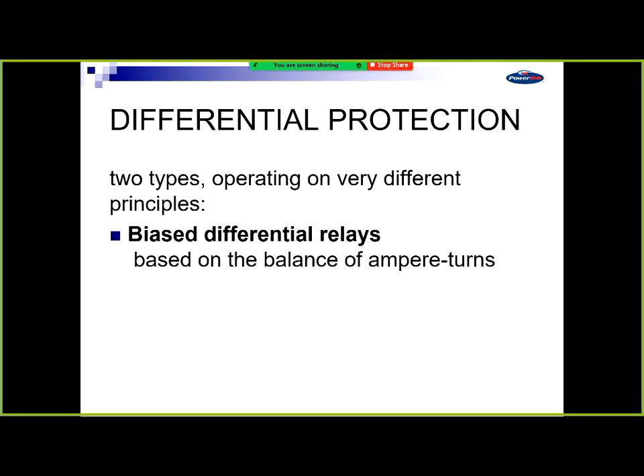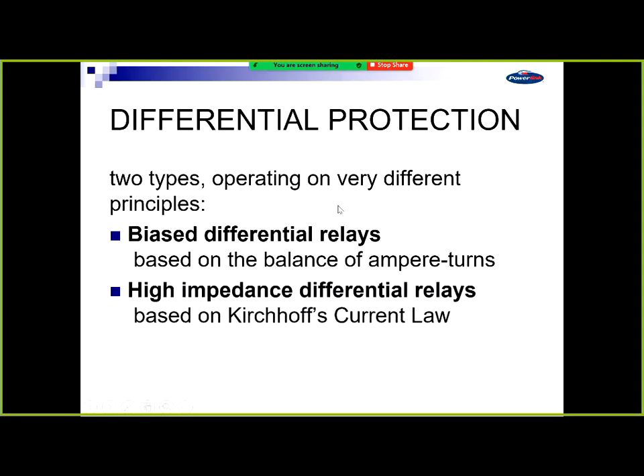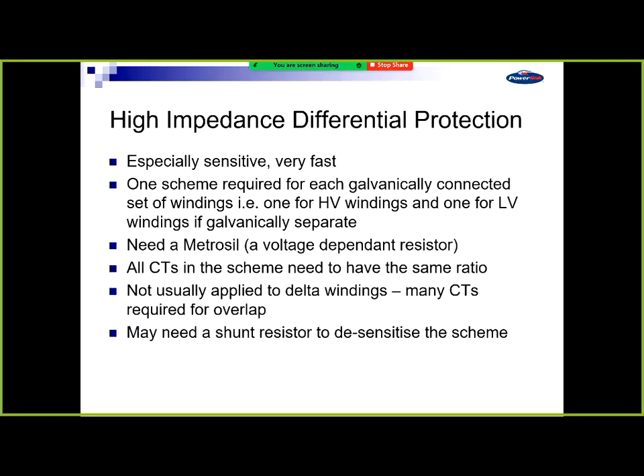Differential protection, there's two main types and they operate on different principles. Bias diff is based on a balance of ampere turns. So that's what we typically use on our transformers. And the high impedance, which is based on Kirchhoff's current laws, is something I used to use when I first started working in protection, but it has now gone out. There's advantages of both of them and disadvantages of both of them, to be honest. High impedance is sensitive, they're fast.